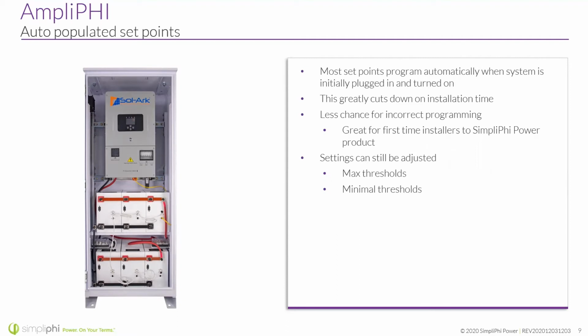Most set points program automatically when the system is initially plugged in and turned on, that's all it takes. Sometimes, like with Sol-Ark, it might require a simple checkbox to say this is a lithium battery. It needs to recognize the battery management system, and it will accept that the BMS will dictate those set points automatically. This greatly cuts down on installation time and there's a lot less chance for incorrect programming. It's something we struggle with in the field all the time - when you're installing a number of different batteries, it can be tricky to keep everything in mind. It's really nice that you don't even have to second guess it; it makes sure there's no incorrect programming. It's really great for first-time installers to SimpliPhi Power products or for battery-based systems in general.